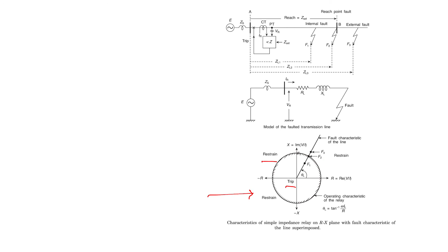So it is obvious that the tripping characteristic of the distance relay to protect the entire length of the transmission line should be a small area on the RX plane, which contains the fault characteristic of the transmission line. Unfortunately, the tripping characteristic of the simple impedance relay is too large an area in the RX plane than ideally required. This is an undesirable trait because it gives rise to maloperations of the relay. So the tripping area is very large, and this is one of the disadvantages of this type of relay.